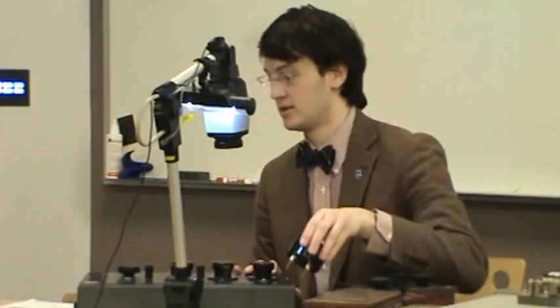Now, normally, for most laboratory applications, you'd be perfectly happy with a meter like this that's direct reading. And so all of these instruments throughout their lives were typically only used in metrology applications for calibration and in finalizing the literature coming with your product after production.